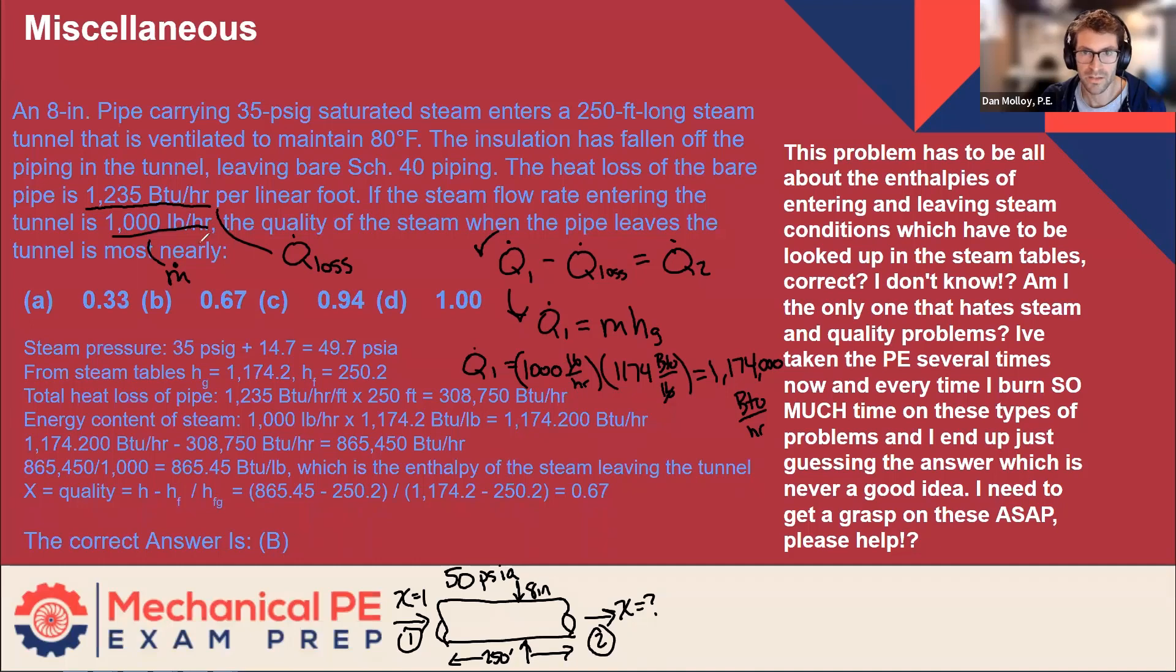Now for the second term, Q loss, we know it's 1235 BTU per hour per linear foot. So let's go a little more detail there. Q dot loss. 1235 BTU per hour per foot, both in the denominator. Times the number of feet. 250 feet is the length of pipe. So for every foot, more losses. Feet cancels and we get BTU per hour, which is the right units for the losses. If we're going to be subtracting that, right, they got to have the same units.